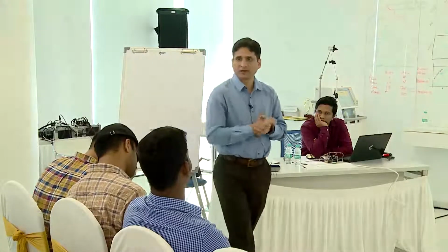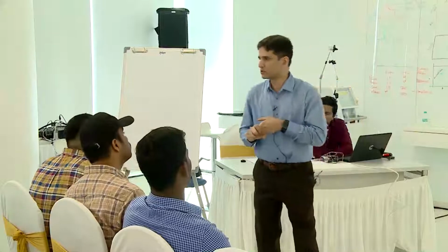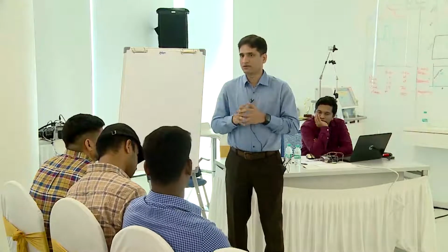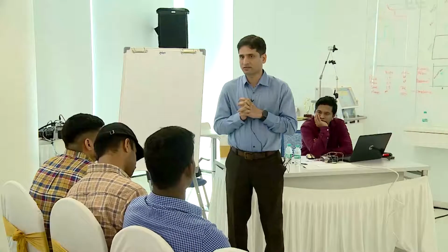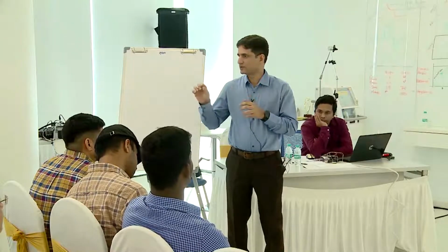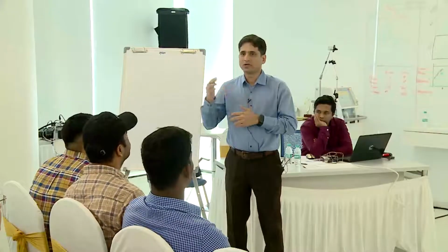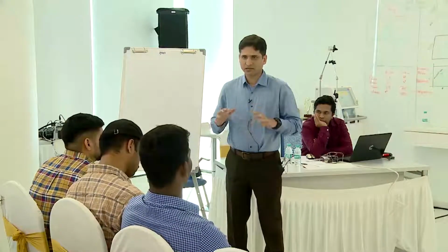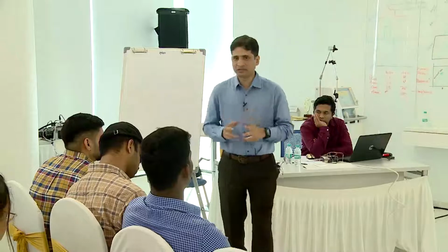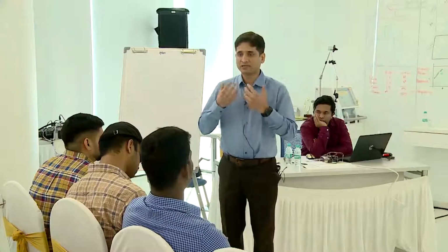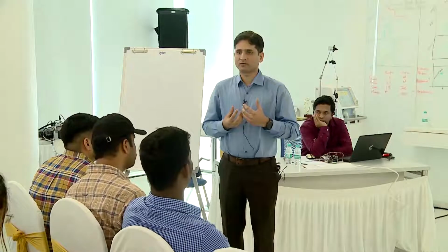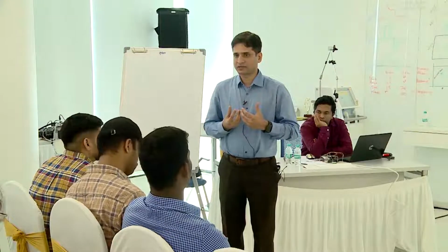So who is the trigger in case of the control mode of ventilation? It is the machine, sensed by time, so it is called the time trigger. If the patient is totally paralyzed and not breathing, it is the time. Because if you have set a particular time, the machine will know that after this time it has to give a breath. That is called the machine trigger breath. But if the patient is a little bit awake, generating a small tidal volume, then along with the machine the patient will also take a small tidal volume. That is called the patient trigger breath.